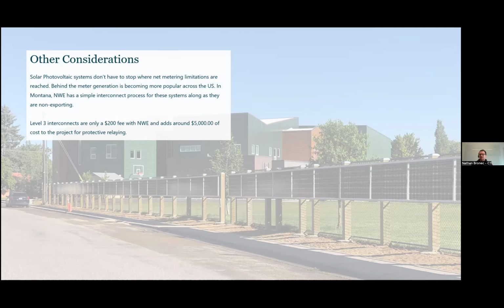The big caveat, though, is what you typically end up having to do is have a protective relay on your PV system that has reverse power protection built into it. So if we are over-generating, it shuts the PV off so we can't push power back to the grid. It doesn't shut off power to the building, it just shuts the PV off.